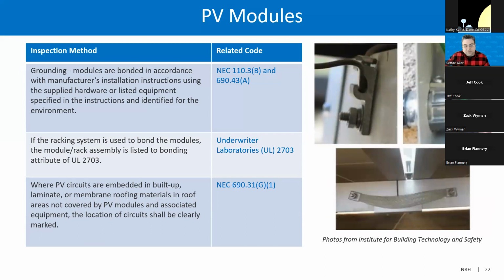The inspector should verify that the modules are grounded and bonded in accordance with the manufacturer's installation instructions. If the racking system is used to bond the modules, the module and/or rack assembly must be listed to the bonding attribute of UL 2703. And the PV circuit locations should be clearly marked.